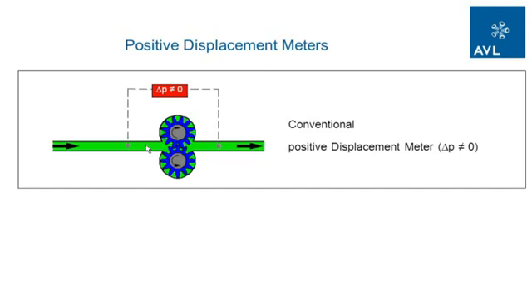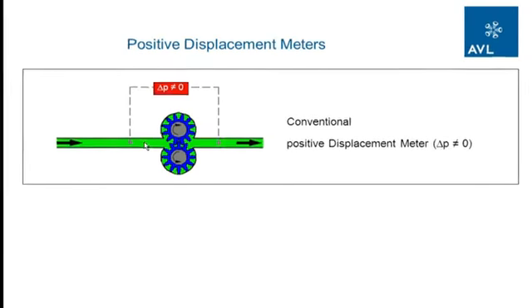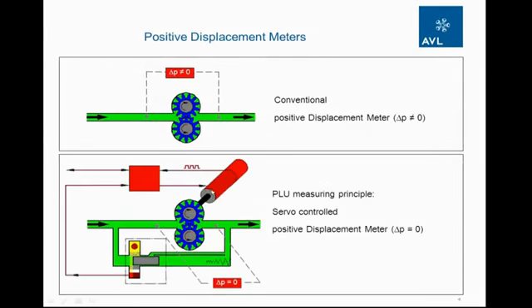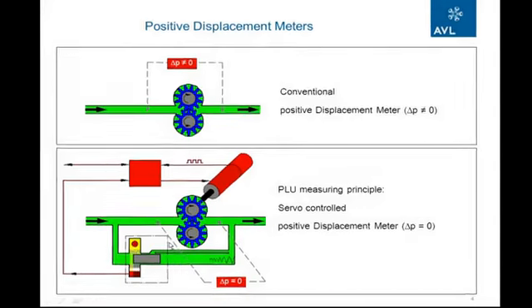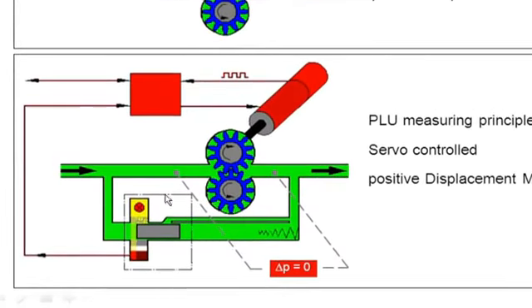And to not have all this limitation, you can use the PLU principle. And with the PLU principle, the servo-controlled positive displacement meter, we are measuring the pressure drop in the bypass and give this information to an electronic, and this electronic will give the information to a servo motor, and the servo motor speeds up these gears just so much that the pressure drop above these gears is zero. And if we do not have a pressure drop, we do not influence the engine, and we have a lot of additional benefits. And this I will explain on the next picture.